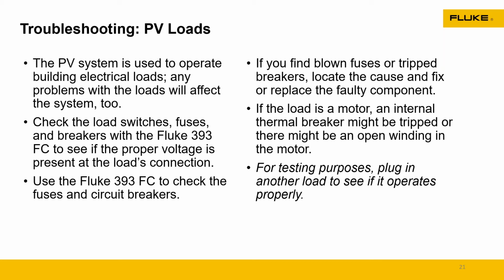problem. You know, for years I worked as an HVAC technician, and when a fuse blew, typically what would be the thing? Well, I'm just going to replace the fuse. Something happened, something shorted. But you really got to do some investigation. You got to do some digging on that and determine what caused that fuse to blow. If you replace the fuse, chances are without any inspection or investigation, the fuse will pop again. So that's where we want to really get out and do some analysis and see what's happening with that.